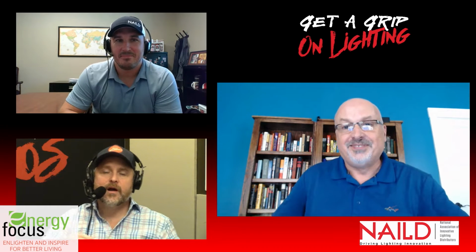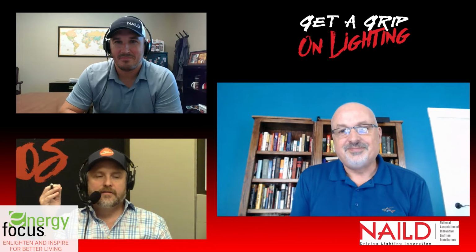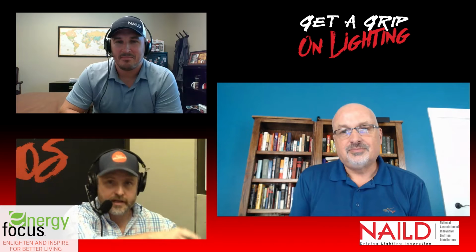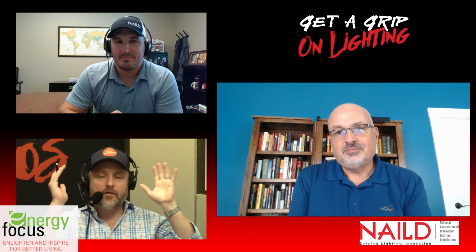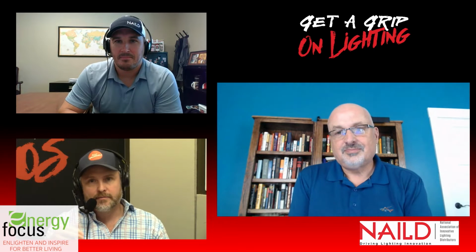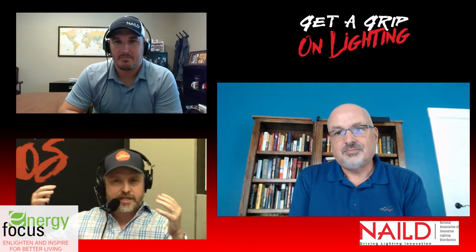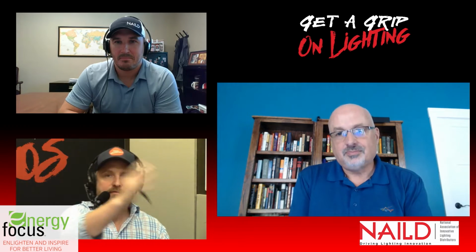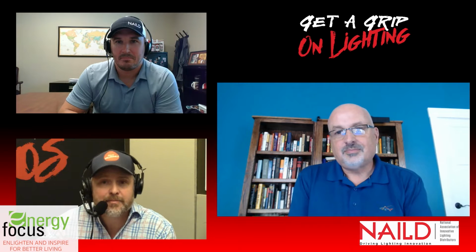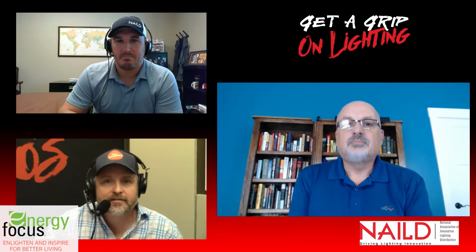I don't know. I was walking through a hospital last week, okay? And this hospital had retrofitted all their 2x4 T8 system. They had an old lighting control system on it. Now they put in all new LED fixtures. Each one had its own sensor, set to a 30-second time delay. And this is not a broad ranging, extended range sensor that sees 50 feet in either direction. It sees maybe 10 feet in either direction, maybe 8 feet. Okay, it's mounted to the fixture. It has a 30-second time delay.